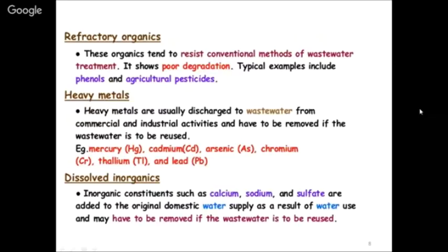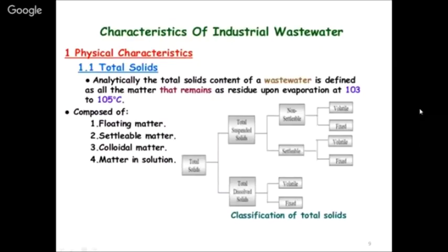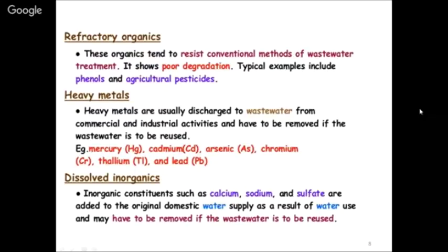Refractory organics resist conventional wastewater treatment methods - surfactants, phenols, agricultural pesticides are all organic in character but are not easily biodegradable. Heavy metals such as mercury, cadmium, arsenic, chromium, aluminum, and lead must be addressed depending on the industry type. Dissolved inorganics - salts like sodium chloride, sodium sulfate, calcium sulfate - are also present in large amounts and must be removed. These are the contaminants of concern that must be identified before treatment can be designed.